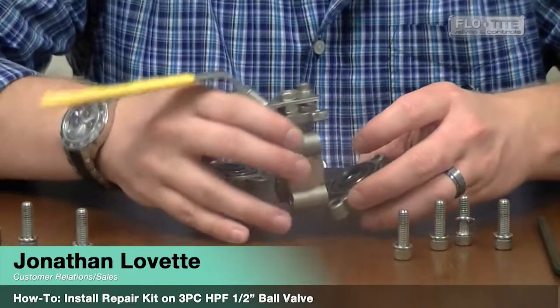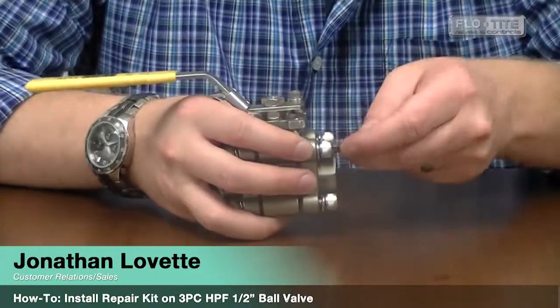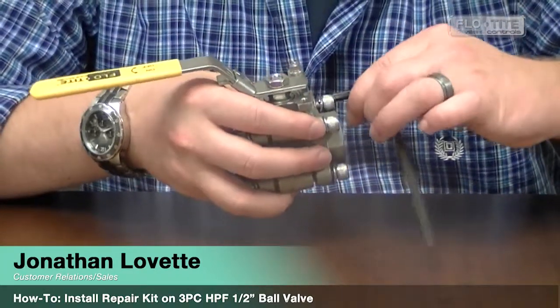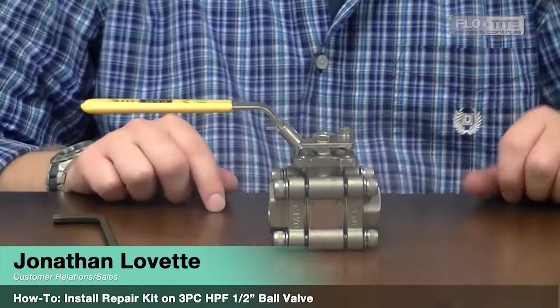With your pipe still spread apart, replace your end caps. Now it's time to tighten the bolts. Remember, when you're tightening these bolts you want to use a crisscross pattern, staging up to 250 inch-pounds. Remove your locking lever handle and cycle your valve a few times just to make sure everything is in line and you have no interference. There you have it — a changed repair kit in an HPF three-piece half-inch valve. Thank you.